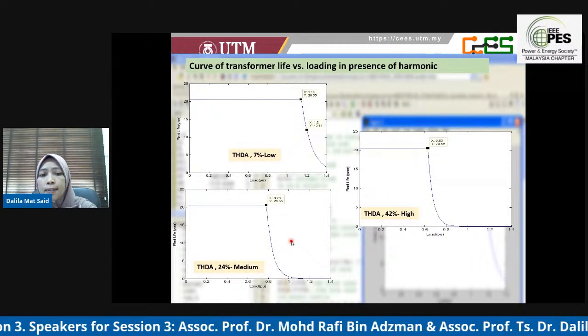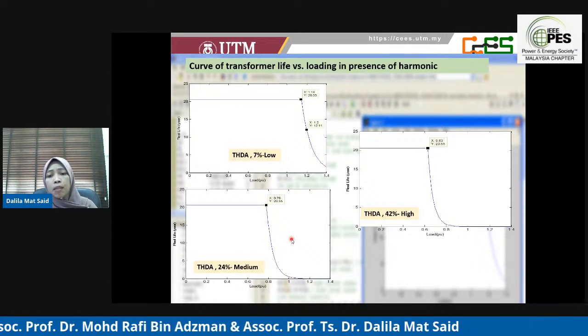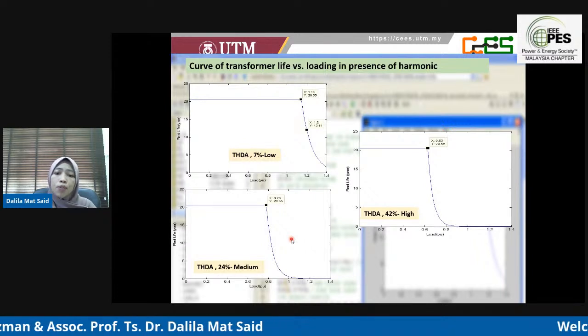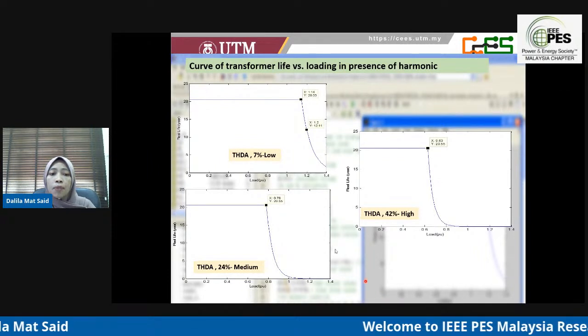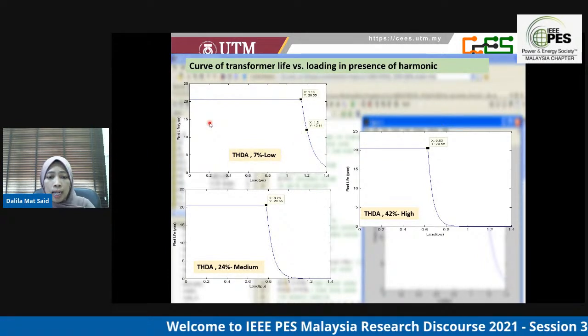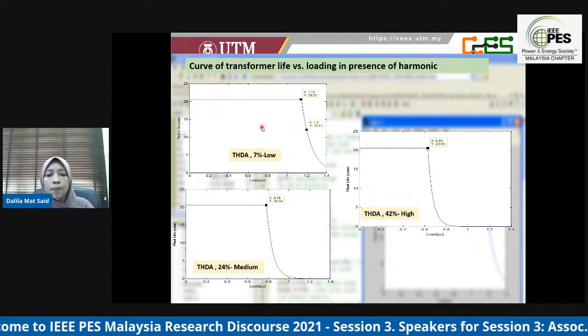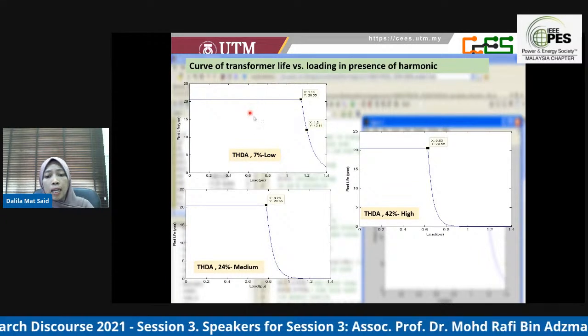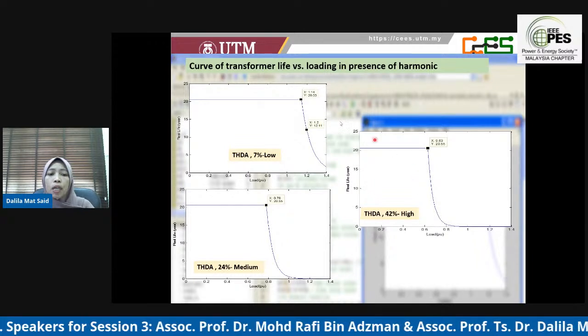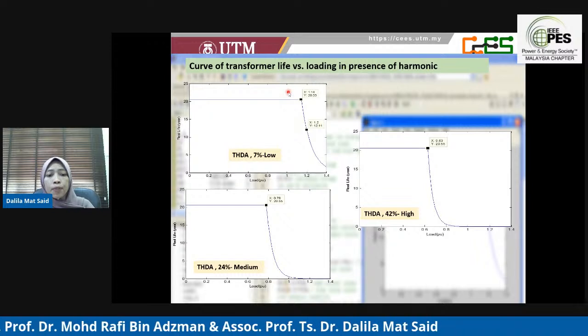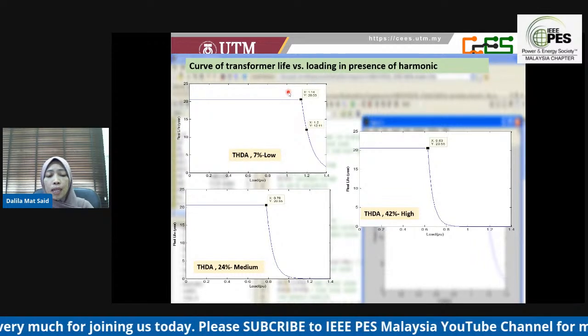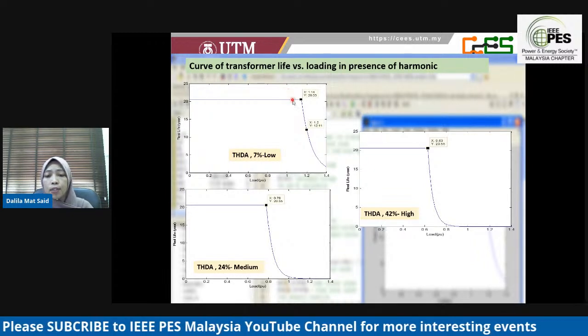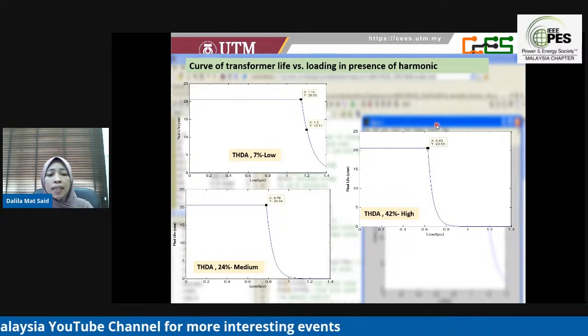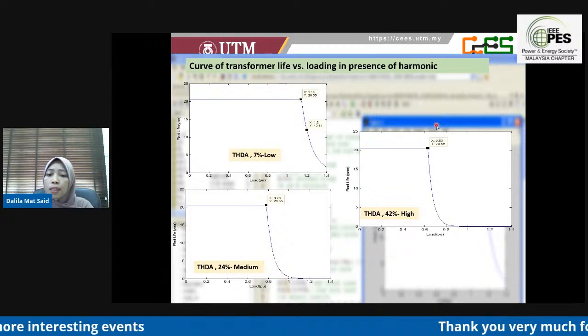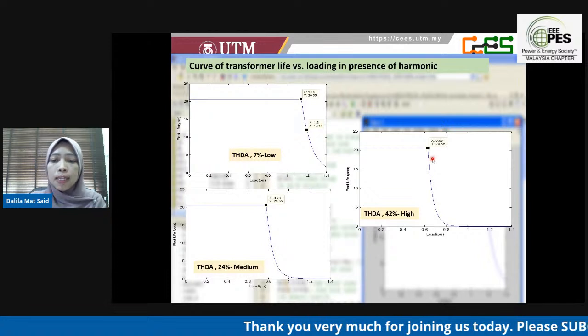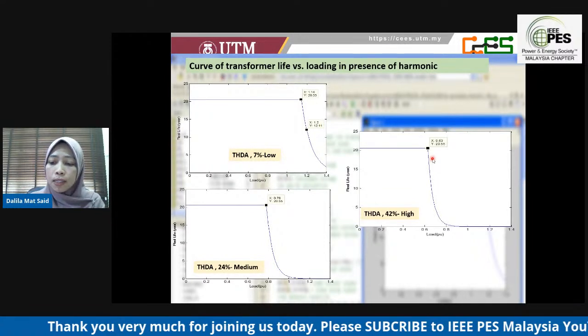From this analysis, the per unit life of the transformer can be determined by referring to the Arrhenius reaction rate theory as mentioned in IEEE standard C57.91. The figures show the transformer life versus the per unit loading. For the first, we consider low, medium, and high THD values. Referring to this figure, for low harmonic distortion the transformer will maintain its normal life until 1.15 per unit. For high THD, the transformer will maintain its normal life until only 0.63 per unit load. So we can see the impact of harmonics on the lifetime of the transformer.